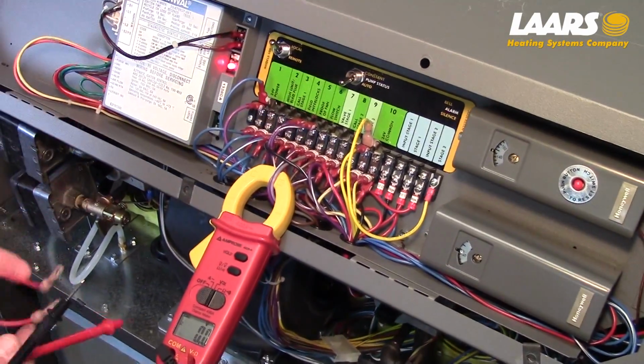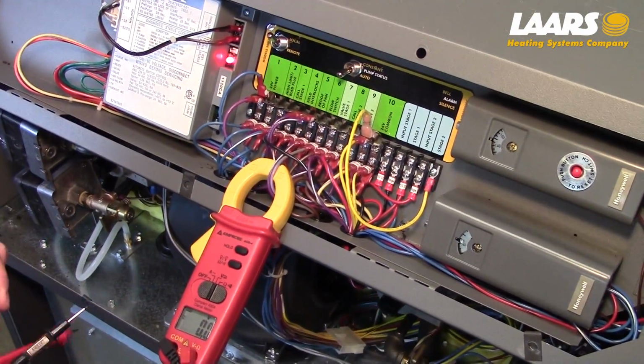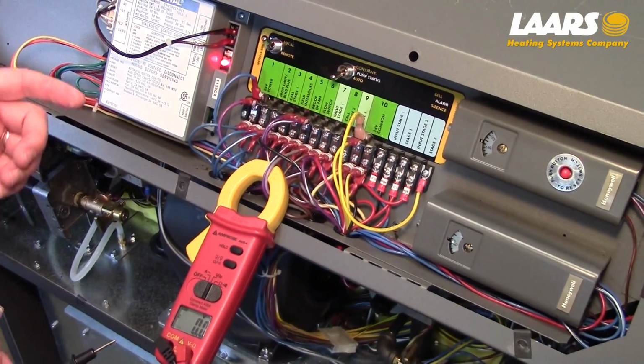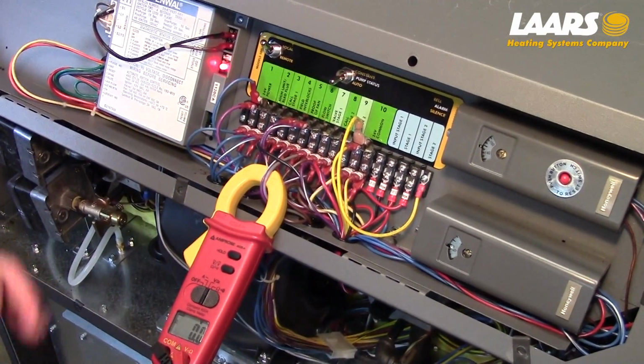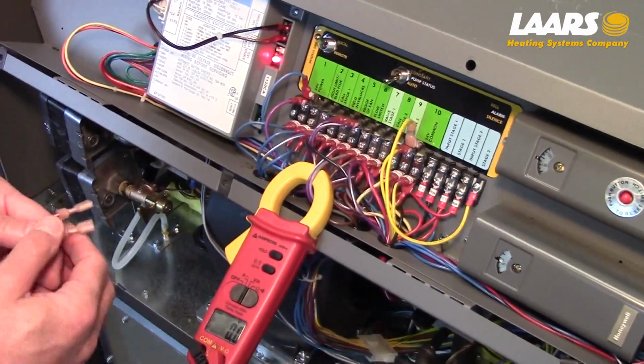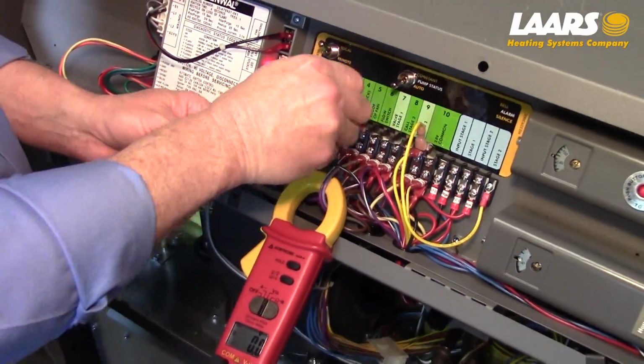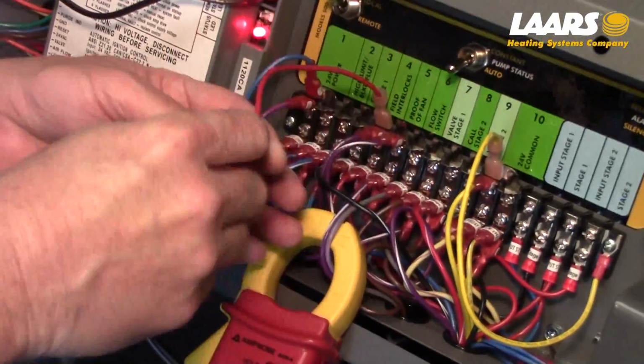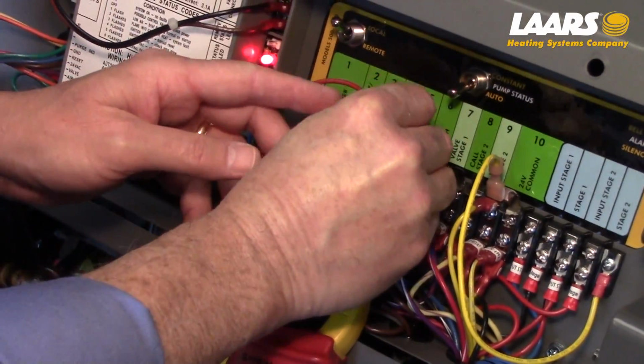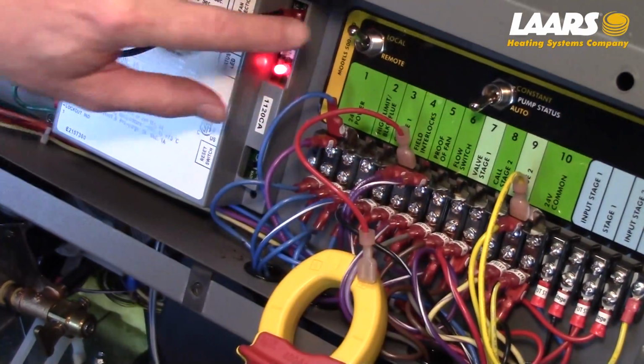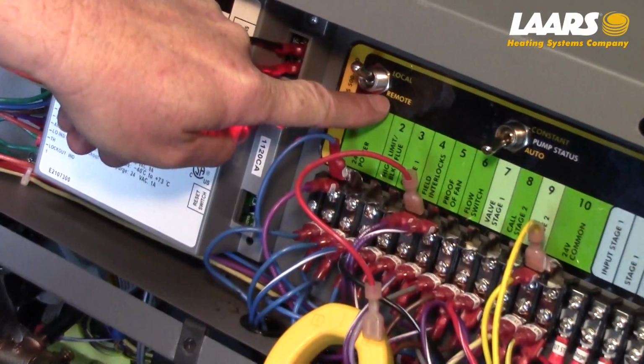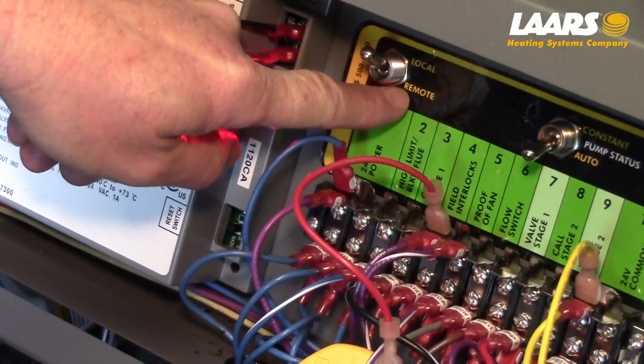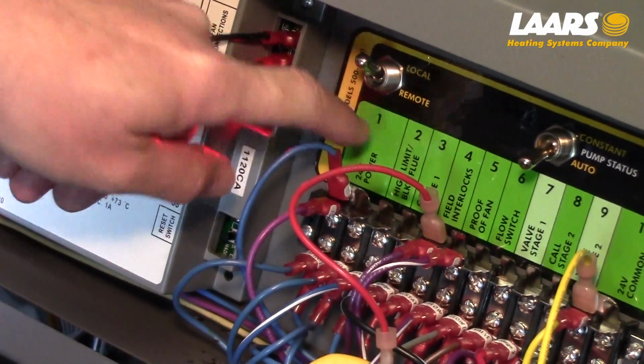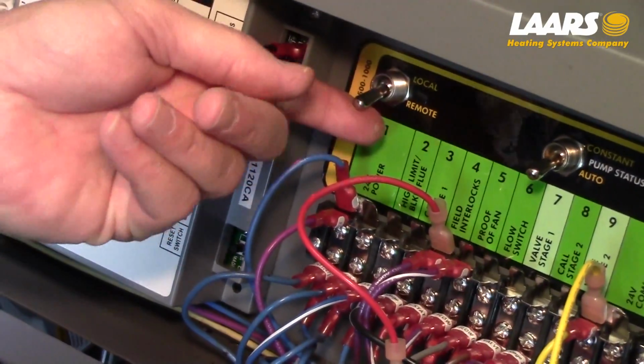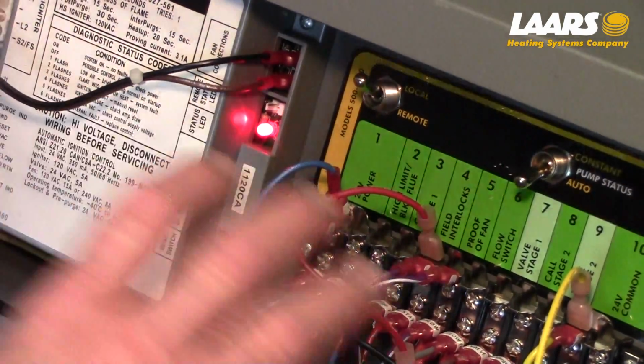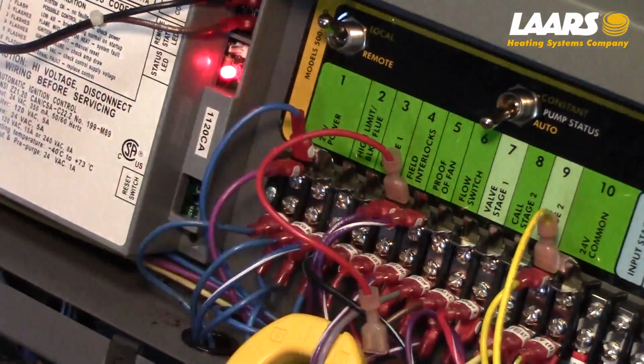However, in the field, you may have an aquastat or energy management may control this. If you're troubleshooting the boiler, remove your field connections and reconnect a jumper lead. Okay? Also, what I want to mention to you is we have local or remote terminal here. If energy management is controlling this for the staging, put it back from remote back to local. That way we're troubleshooting our boiler, not the whole system yet.